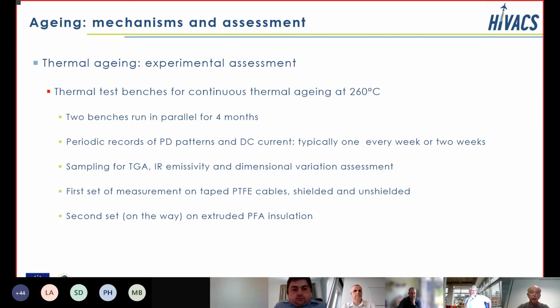So we have built two thermal test benches for continuous thermal aging at 260 degrees and run in parallel two aging tests on two cables for months. During this time, we periodically recorded PD inception voltage and patterns and the DC current, typically once every week or 2 weeks. And we also took samples for physical chemical measurements.